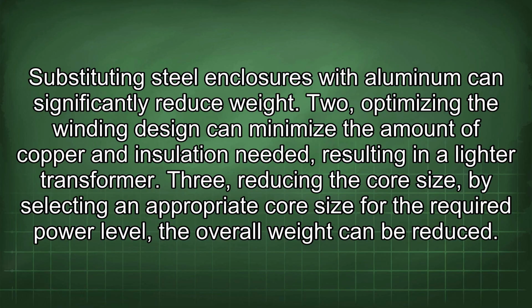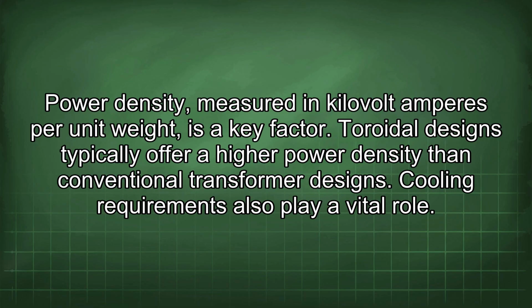2. Optimizing the winding design can minimize the amount of copper and insulation needed, resulting in a lighter transformer. 3. Reducing the core size. By selecting an appropriate core size for the required power level, the overall weight can be reduced. Power density, measured in kilovolt amperes per unit weight, is a key factor. Toroidal designs typically offer a higher power density than conventional transformer designs.